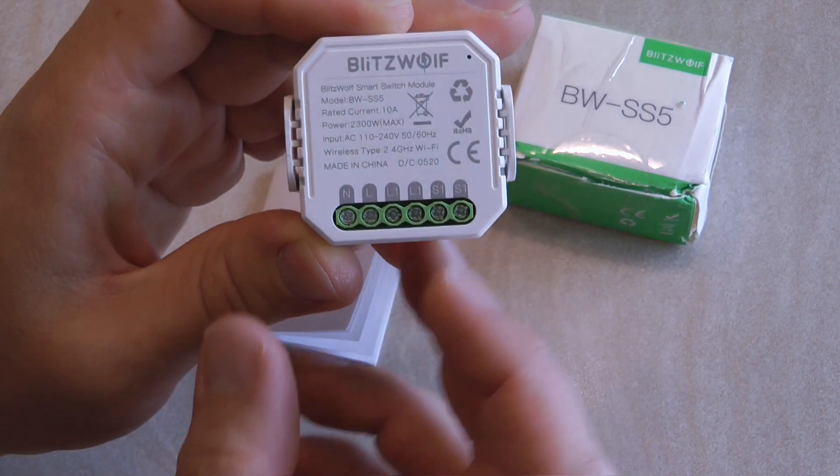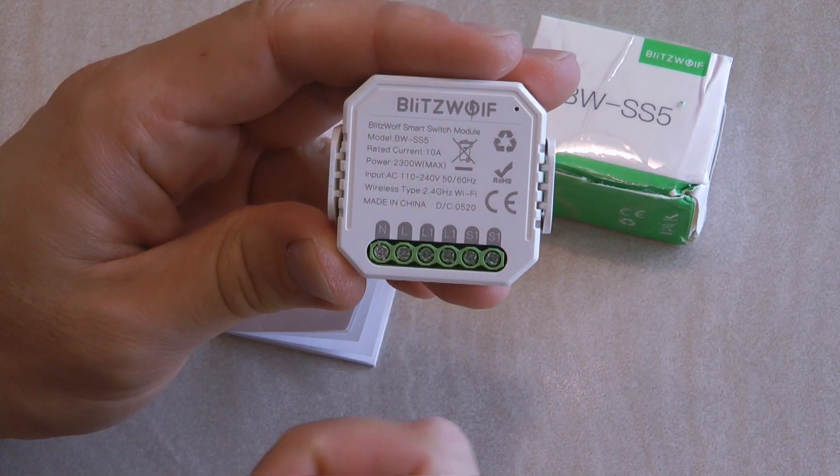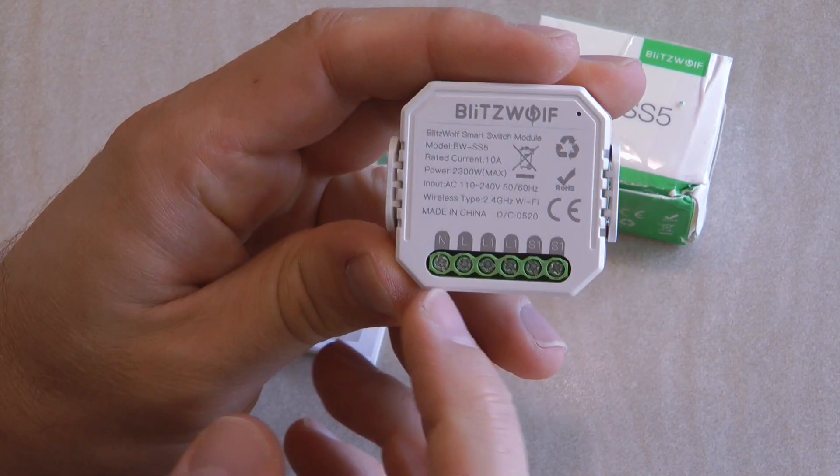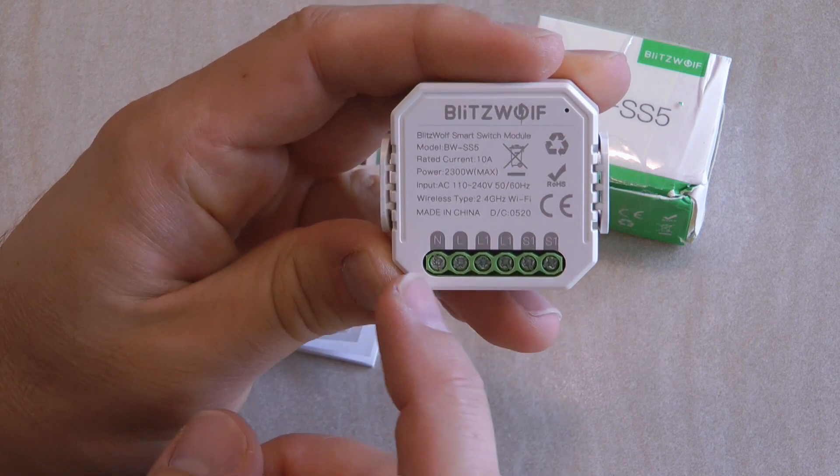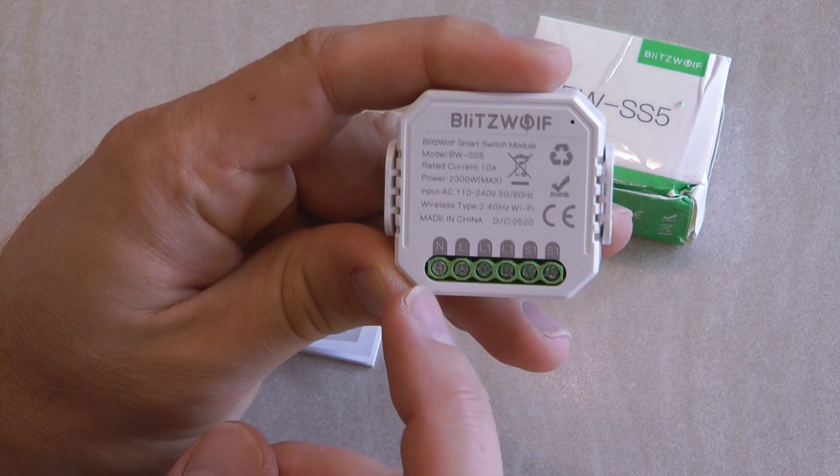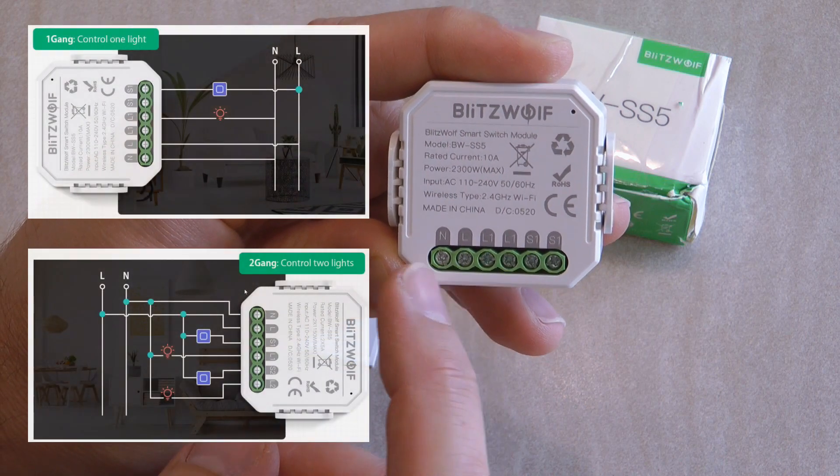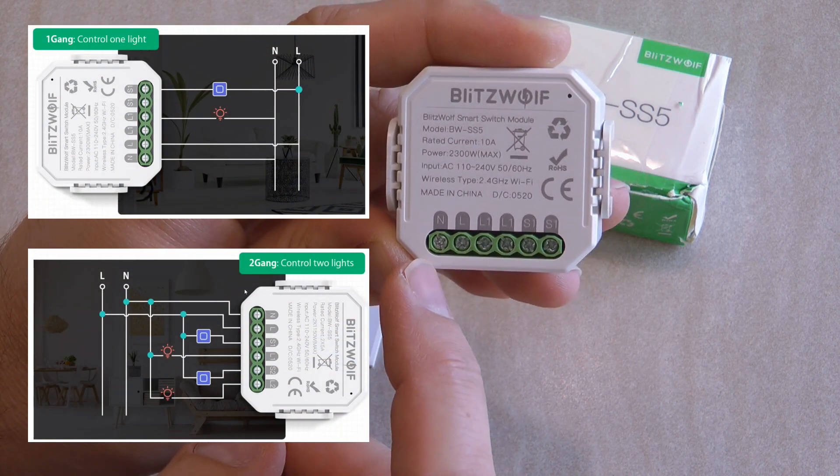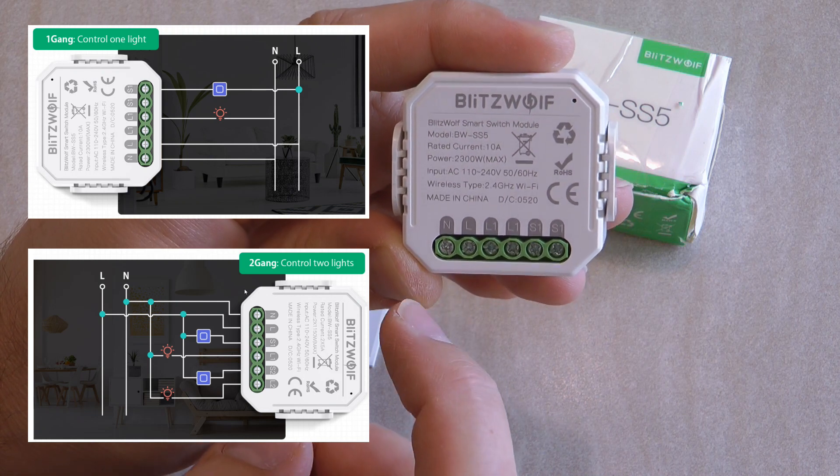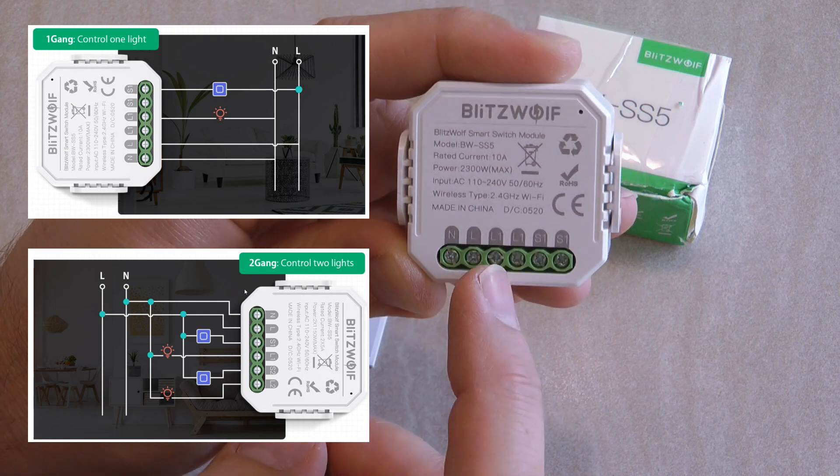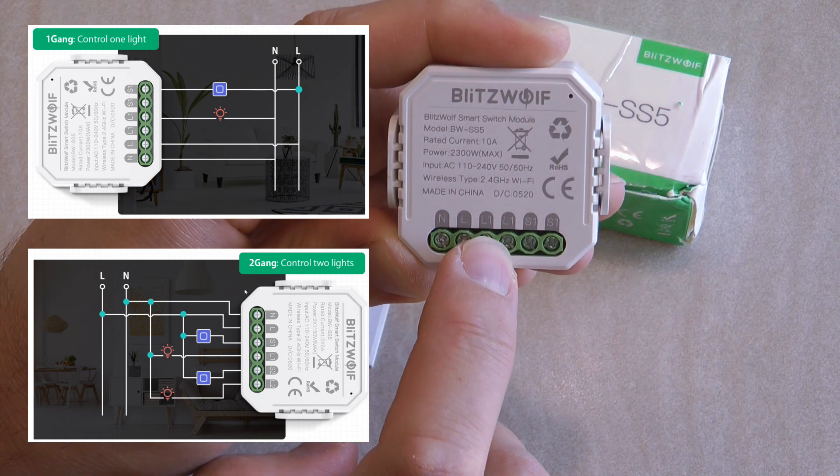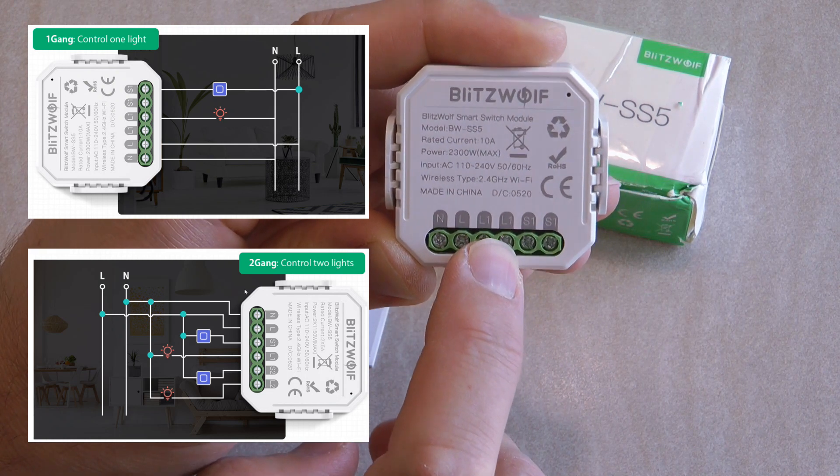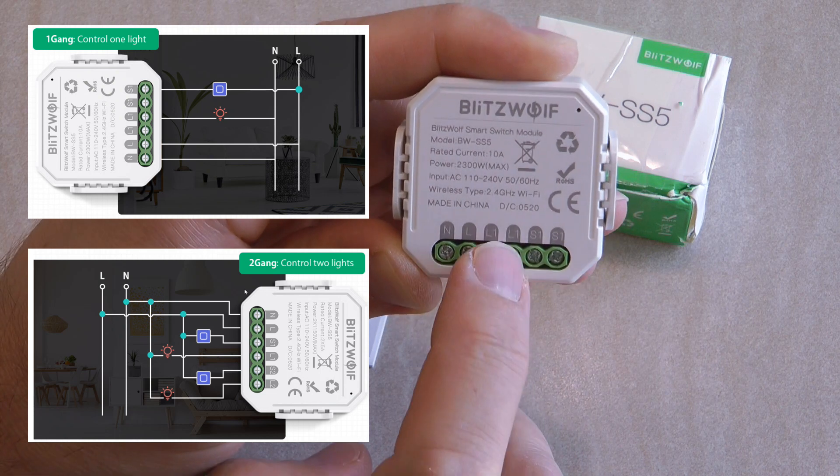Let me spend a little bit of time just to explain how you wire this unit up. Starting from the left, you have an N and L connection - neutral and live - where you connect your fixed mains supply. The next two connections are labeled L1 and L1, or in a two gang version L1 and L2. These are the outputs that go to your lamps, the switched live lines.